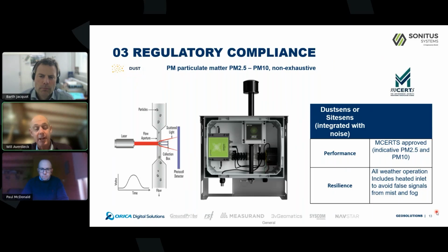So this technique has the great advantage that it can simultaneously measure PM2.5, the particles less than 2.5 micron, and also the PM10. We can also look at respirable dust and total suspended particulate as well. The middle is showing an implementation of such an optical particle counter in our Dustsens. There's an inlet where it's taking air from all directions. Flow is from the top going down, pulled by a fan through the optical particle counter.